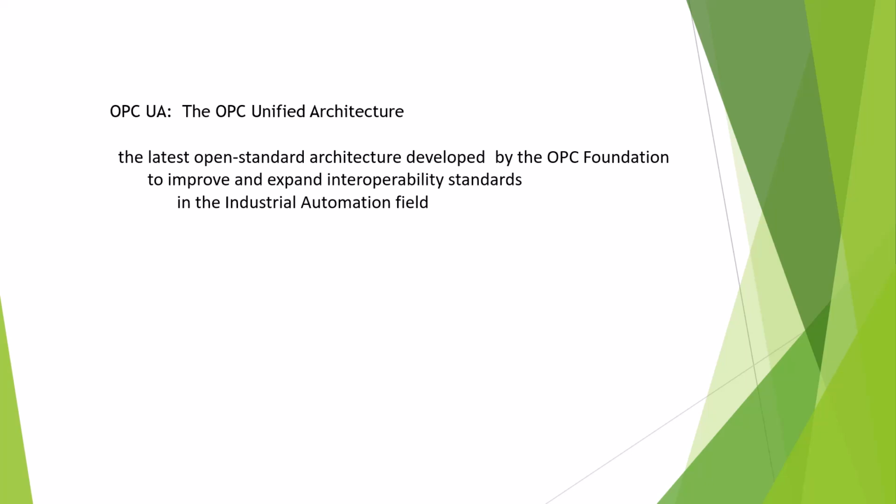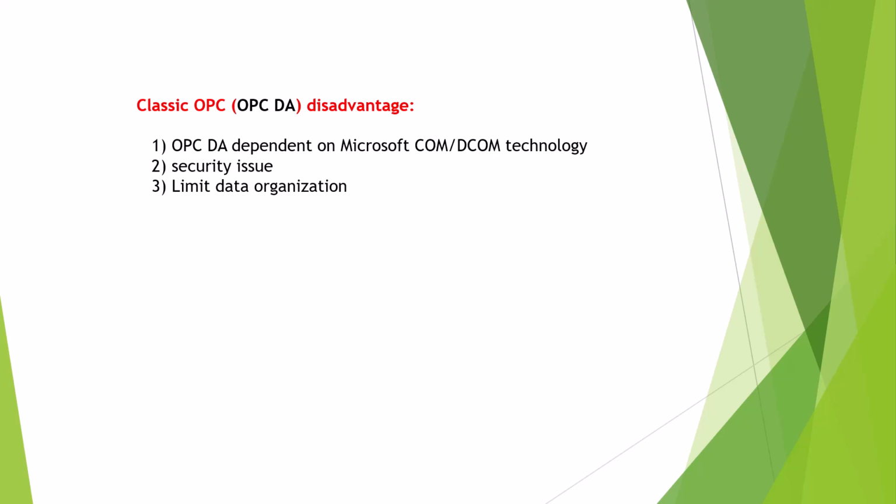So first we should know the disadvantages of OPC DA, classic OPC. First, OPC DA depends on Microsoft DCOM technology, so it only works on the Windows operating system. Second is the security issue, which is a very big trouble. Third one is the data organization limit.